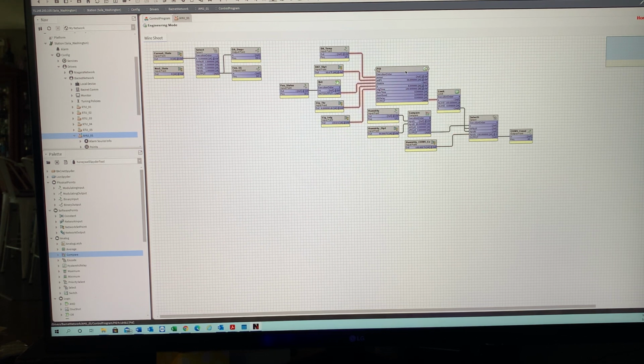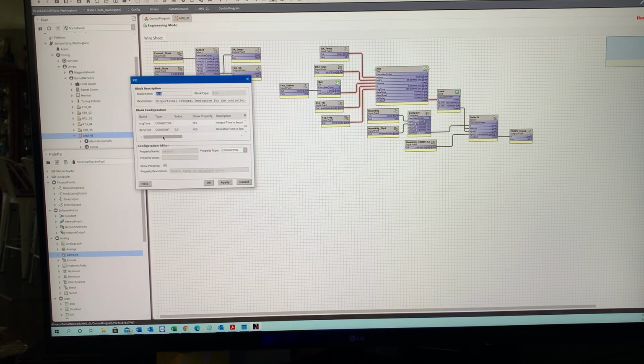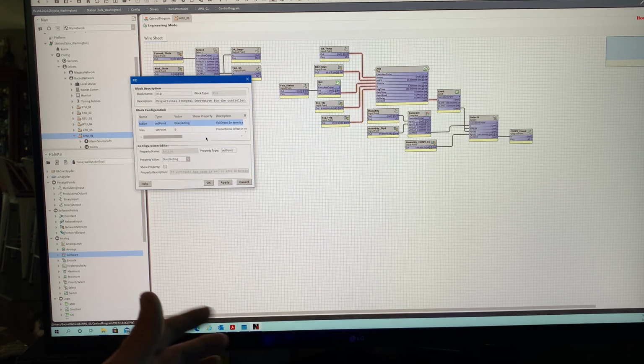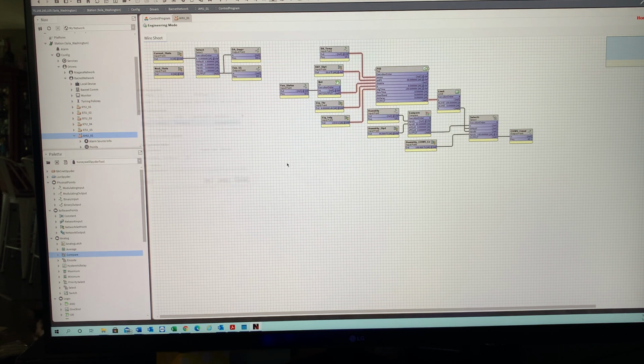So we can go into here -- also, there was something I wanted to show you in the PID. There's the action for the set point: do we want it direct acting, or reverse acting? Basically, for heating and cooling, it changes the way the output of the PID works, depending on what you're trying to maintain for proper function of the PID.